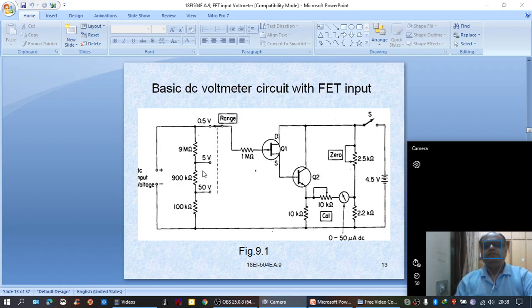So when you adjust for two positions, automatically for the third position, that is when the input voltage is 50 and the range switch is in position 50 volts, obviously this pointer has to be at its full scale mark. So the device is calibrated and is ready for use. First, with the zero input, zero adjustment is done by this 2.5K, and by using this 10K pot, span adjustment is done. That is, with full voltage applied, full scale deflection on the scale.